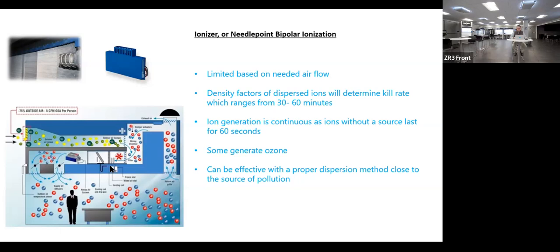If these companies were to generate the amount of ions necessary to actually disperse them properly through the HVAC run, however long that may be, down to the facility and spray these hydroxyls along the rooms, they would generate so much ozone, it would be deadly to the human body. You can't do it. Again, applying technology where it does not belong. So be very, very cautious of these technologies, even air filters that say they have ionizers in them, because some of them even today still generate ozone and other organic substances that it reacts with.